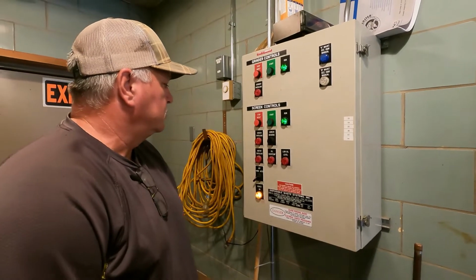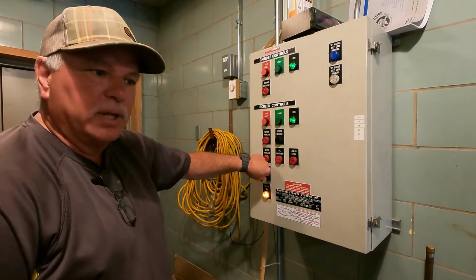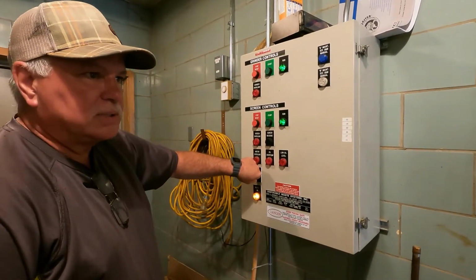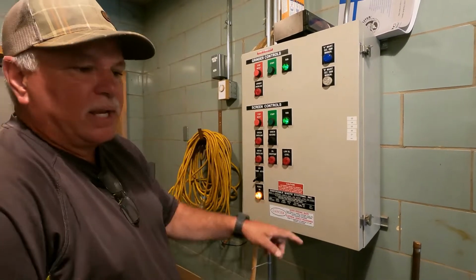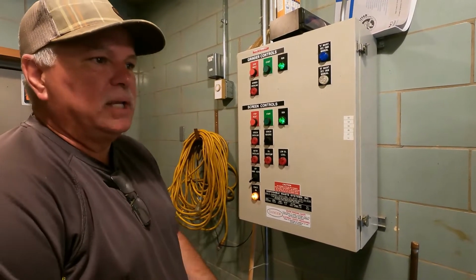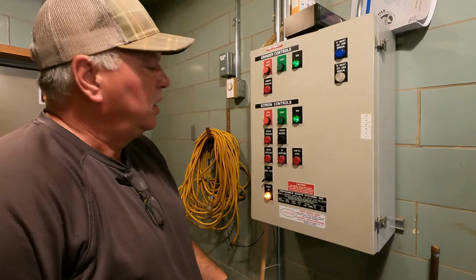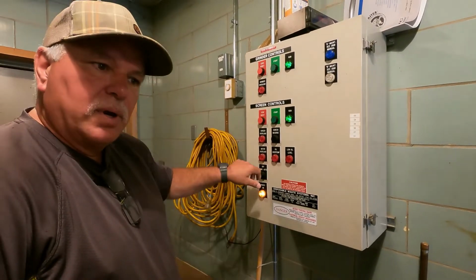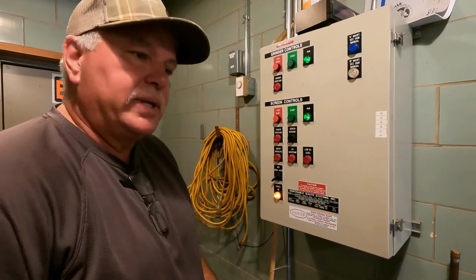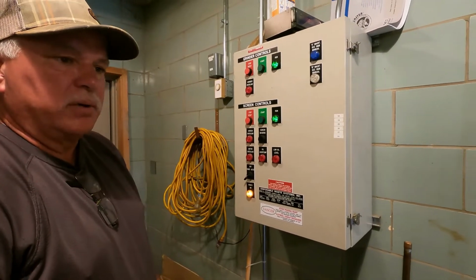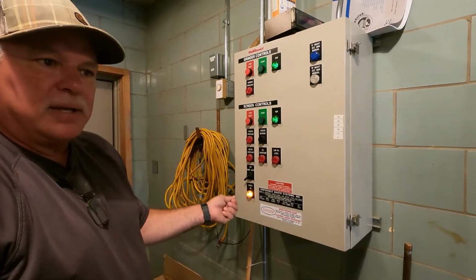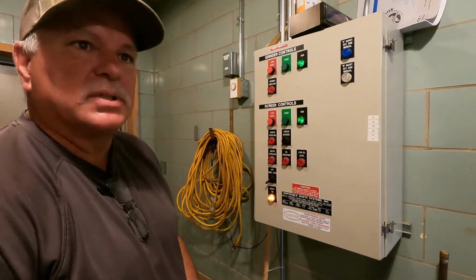So, another hands-off auto: you can run in auto, which basically runs it all the time, but it would let it kick some if there's debris in there that's grinding or jamming the grinder. In auto, that grinder would automatically try to reverse itself 3 times to clear the jam. In hand, it basically runs all the time no matter what's coming.